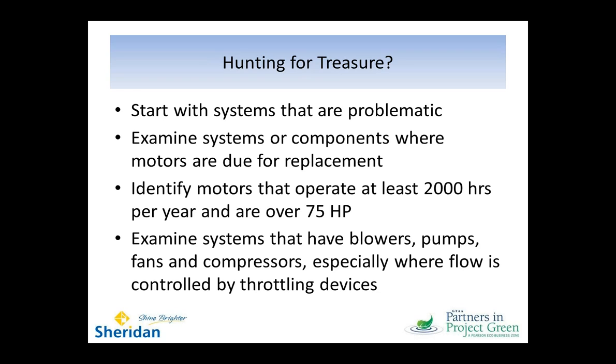You can also look for systems and components where you know the motors are due for replacement. They've been out there for 20 years. They're barely holding on, but you've kept them going. Now it's probably time to get some premium efficiency stuff in there and really look at opportunities for sizing. And you want to look for motors that are operating over 2,000 hours a year and over 75 horsepower. The economics are going to work in your favor for replacing those. And then finally, because of those affinity rules, you're going to look for systems with blowers, pumps, fans, and compressors, and particularly those systems where you've got throttling devices in place instead of variable speed drives.